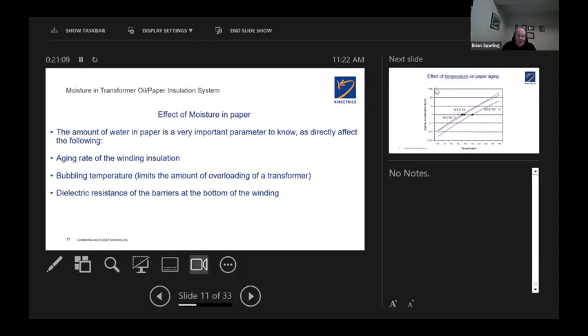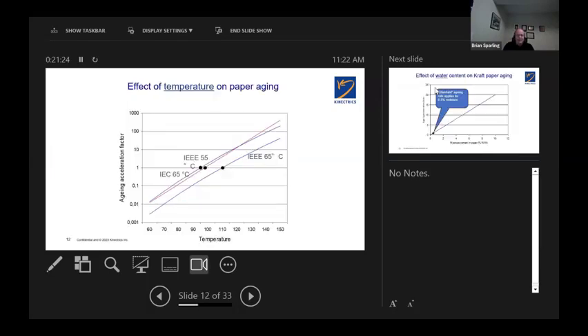So this effect is where you need to understand how wet is the paper, because it affects the aging rate of this winding insulation. It definitely influences the bubbling temperature. We'll touch on that. And also the dielectric resistance of the barriers at the bottom of the winding. This is from the IEEE loading guide and the effect of temperature on paper aging. What we see here is aging acceleration factor. So you see the number 1 there, and you see 3 dots.